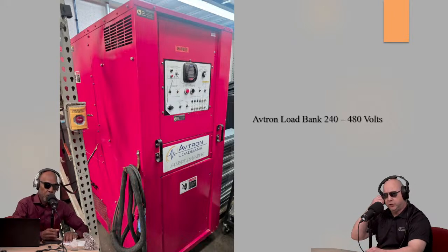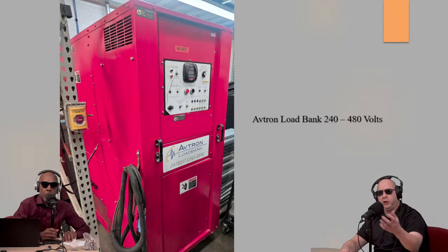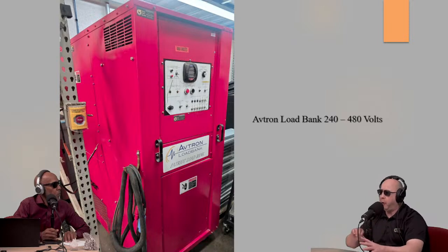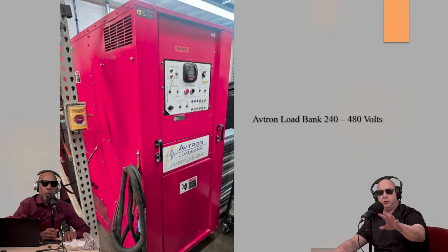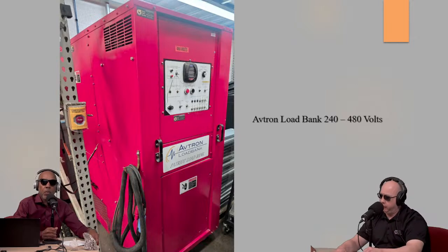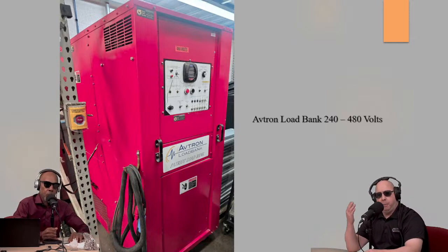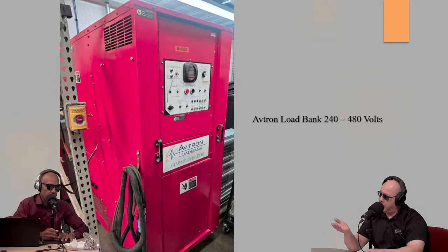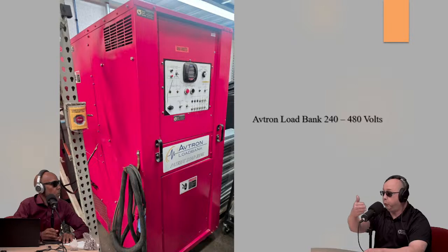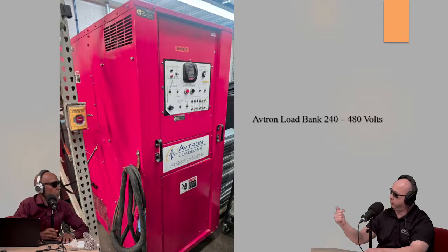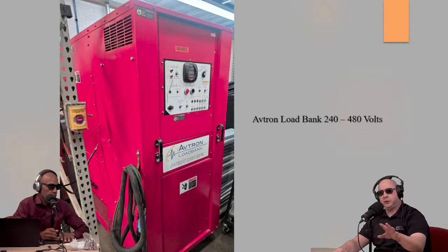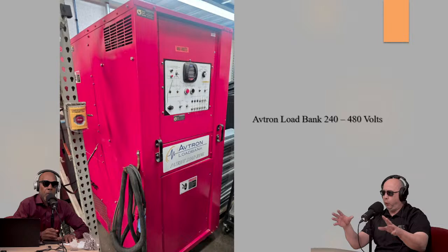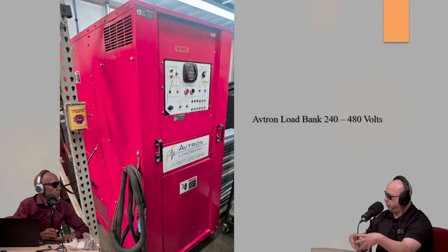We use this unit for our three-phase systems. We hook it up to the output, turn on your UPS, and then turn on the load, providing output power to your equipment. This simulates the equipment you're hooking up to it. We can do 240 volt systems and 480 volt systems, and based on how many power modules you have, we can select a load percentage to run to the unit to simulate what you've got in the field. This allows us to have one-stop shop for all types of equipment that's going to hook up to a UPS.